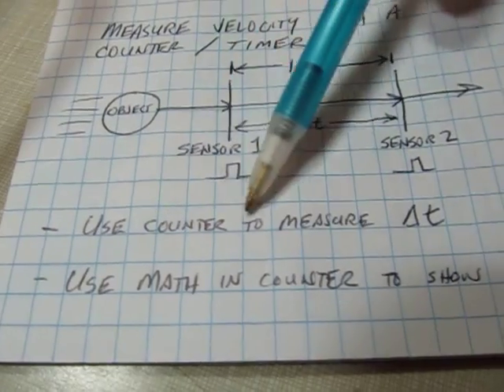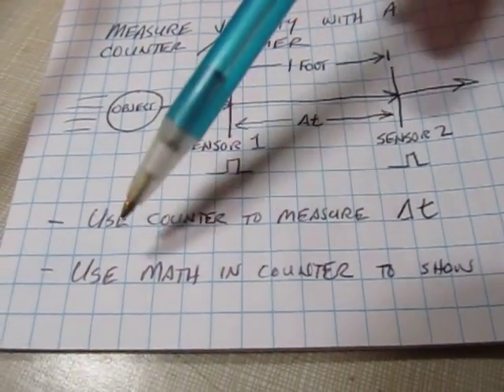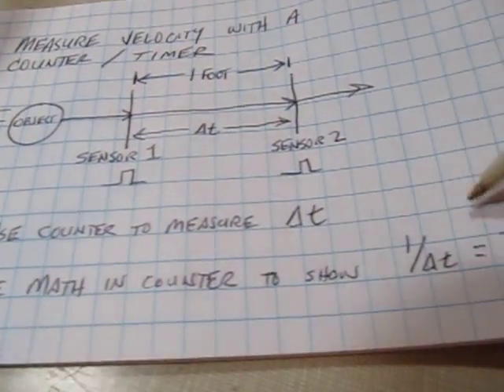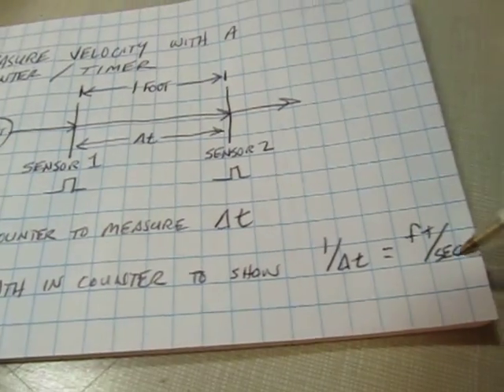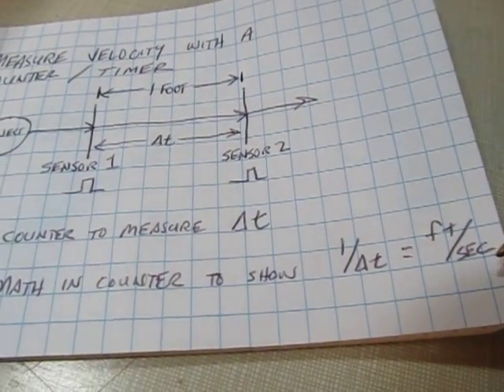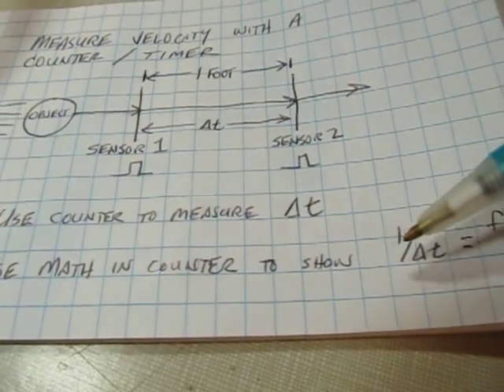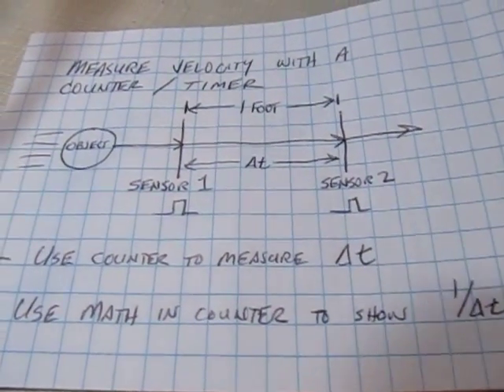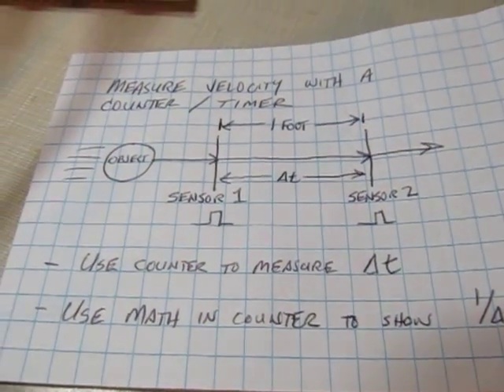We can use a counter to measure that time interval. This counter also has math capability that allows you to invert that to 1 over Delta T, which will directly read out in feet per second. If you have a counter that doesn't do the 1-over math, you just do that calculation yourself.